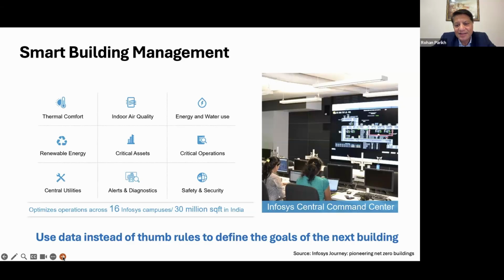Unless we have access to data and alarms, and unless we stay on top of ensuring sensors are calibrated and working properly, it's very difficult to trust the building management system. My experience globally is that building management systems don't truly deliver what they promise, and it's not the fault of the system or sensors, it's the fault of the person operating it. They don't pay attention, don't diagnose faults, and it compounds—garbage in, garbage out—until complaints mount and people lose faith in the system and give up on it.